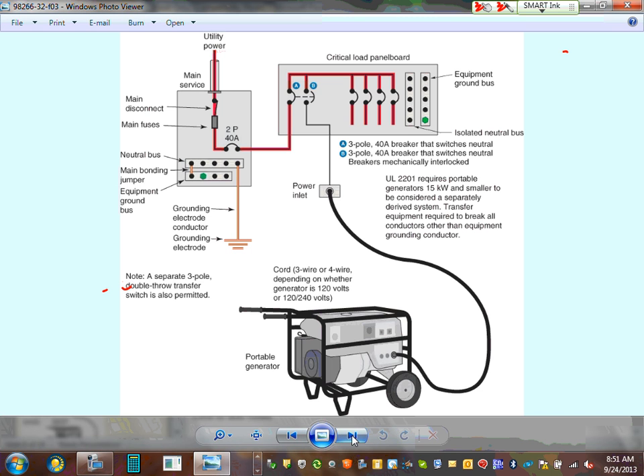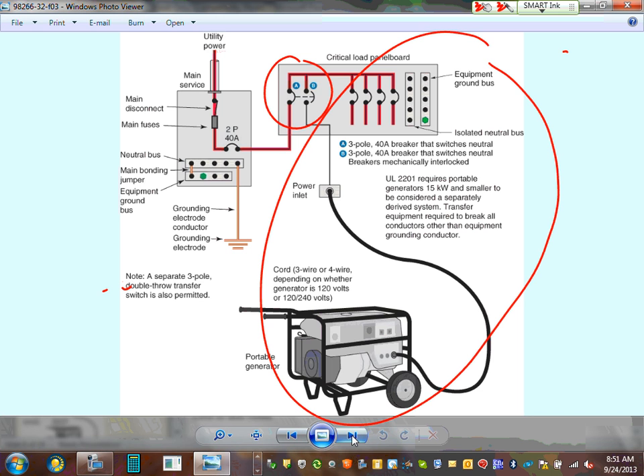When you lose power, you walk to your basement, you flip these switches. Now here's utility on, generator off. You go flip them the other way. Then you walk outside, start your gen, plug your gen into this power outlet, twist it, and now all your loads are up and running. Typically, we do it in this order, though. We start the generator, plug it in here, and then go down to your utilities room and flip the circuit breakers. Now all these loads are powered from the generator, only these loads.